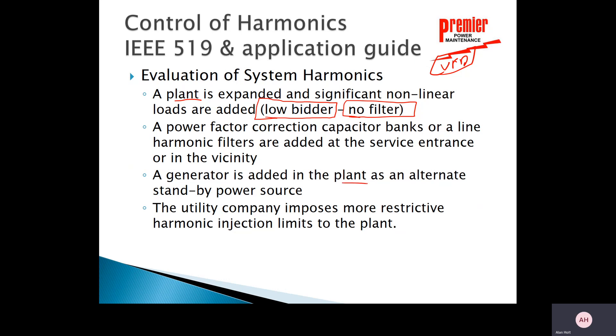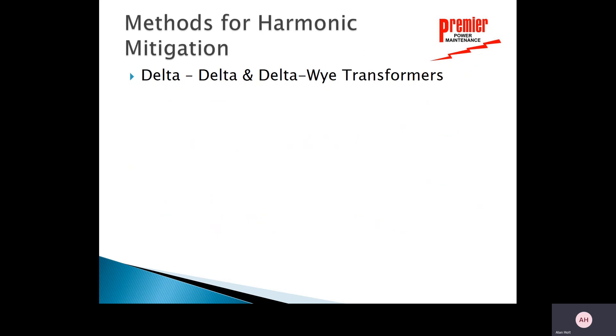If a generator is added to a plant as an alternate standby source, it can heat up much faster due to harmonics. The utility's equipment is robust enough to handle it, but the utility may start imposing harmonic injection limits. At a Nucor facility in Alabama, the utility was concerned that improper filtering on a backup yard would cause problems on their 500 kV grid, so remediation was required.